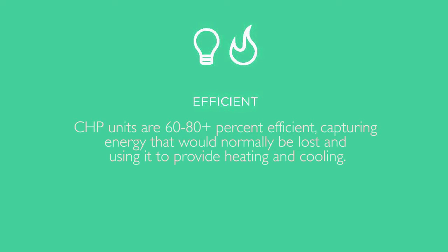What we've done, going through the heat balance calculations, we're right at 78 to 78.5% efficiency. And that's measured in a higher heating value, which is different from manufacturers. They use a 10% higher number. So it's 78, 79% efficient compared to 50 to 55% efficient for the most efficient power plant built by utilities today.